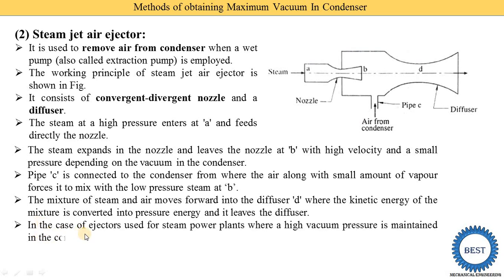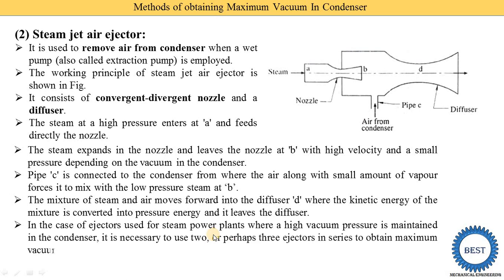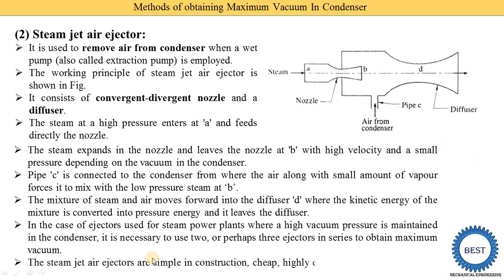In the case of ejectors used for steam power plants where high vacuum is maintained in the condenser, it is necessary to use two or three ejectors in series to obtain maximum vacuum. If the size of the condenser is larger, more ejectors connected in series are needed, each also connected to the condenser for removing the air. The steam jet air ejectors are simple in construction, cheap, highly efficient, and have no moving parts.